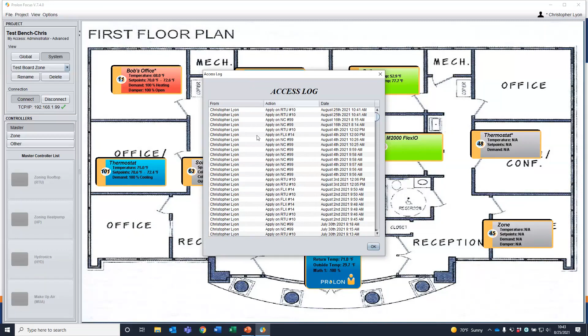We have the ability to take a snapshot. Once the contractor is satisfied with the commissioning of the system, we're good to go. That snapshot is a freeze frame of every single controller in the entire network as it sits exactly then, and we can use that as a restore point. Say if something gets screwed up in the future, somebody changes something and doesn't know what they did or how they made it stop working, we can use that as a restore point.